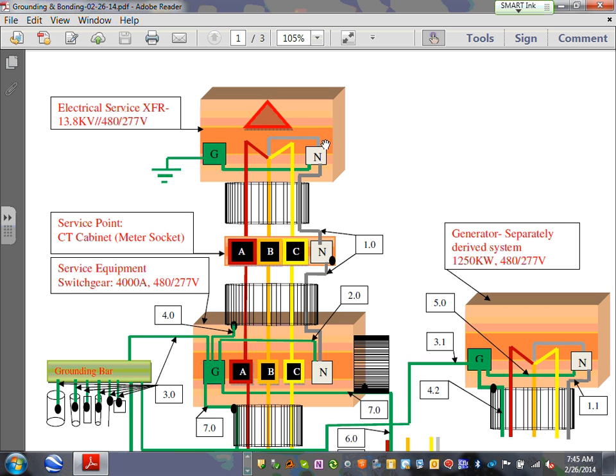So starting from the top, Adam, the first thing you're going to encounter right here is a typical power system coming to a building. Typically, utilities will give you a delta-Y transformer. Can you guys see at the top? This transformer is the utility transformer, Matt, that you put outside on the site. That transformer is typically 13,800 volts on the primary and on the secondary 480/277. Can you guys see that? Everybody can see that?